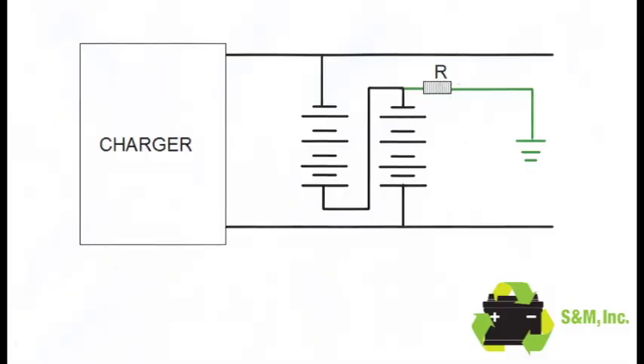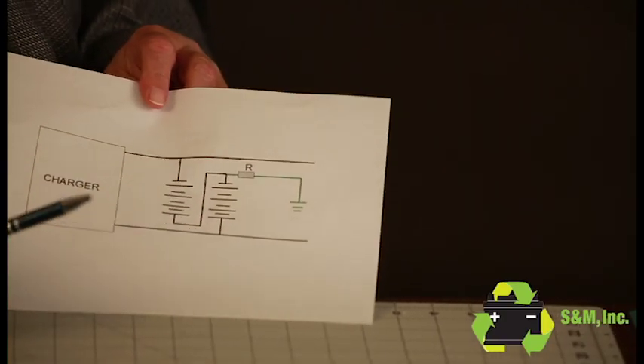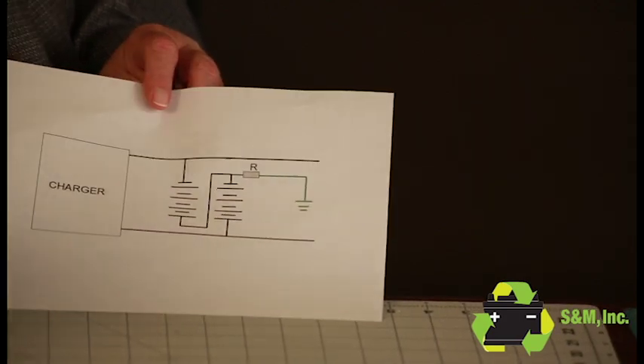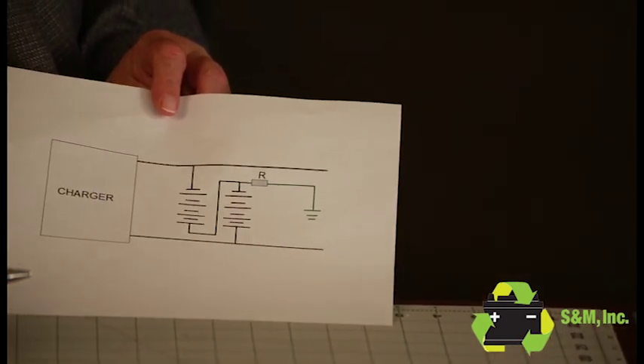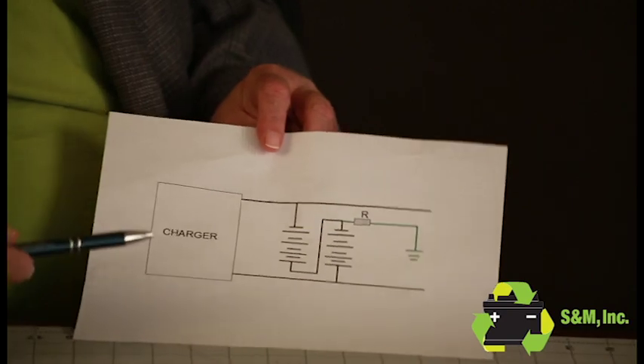Another thing done sometimes in telecom, being considered for higher voltage DC systems like the 384 volt systems turning up in data centers, is they'll take half the string and center tap it with a resistance ground, then the other half of the string. So the charger's putting out 384 volts, 390 volts, whatever it's doing in that higher voltage range. It's almost like a UPS front end.